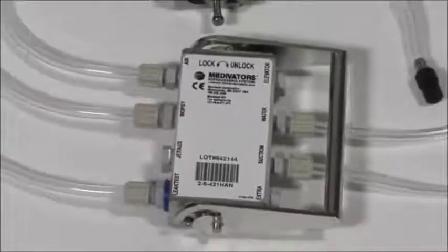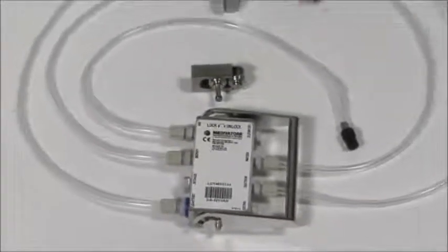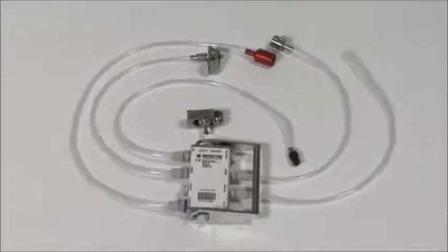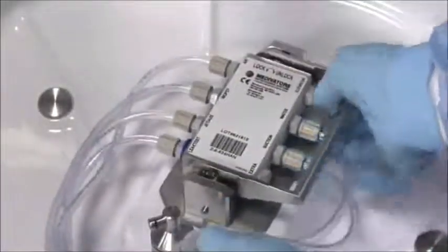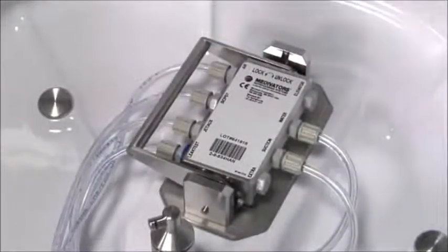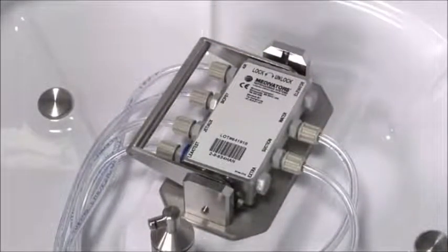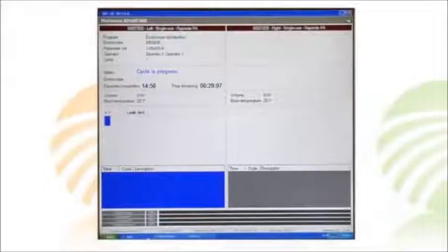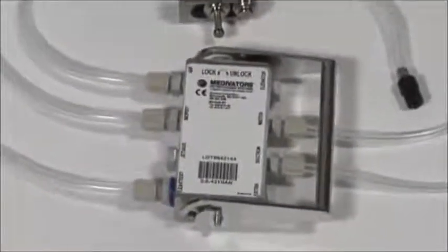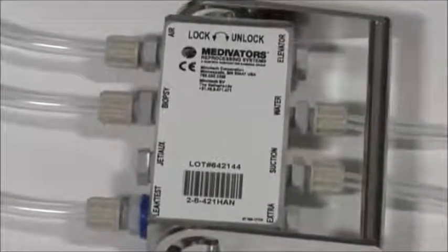Advantage Plus hookups connect to the channel manifold and are designed with channel-specific tubing and connectors, which are labeled on the connector block. With individual channel connectivity, fluid and airflow can be regulated per the parameter settings programmed into the computer system. These parameter settings are necessary to achieve high-level disinfection and are specific to each endoscope. The computer system then monitors the channels and can determine if there is a blockage, a leak, or even if a connector pops off. Each endoscope model or family requires a unique hookup block to ensure proper disinfection can be achieved.